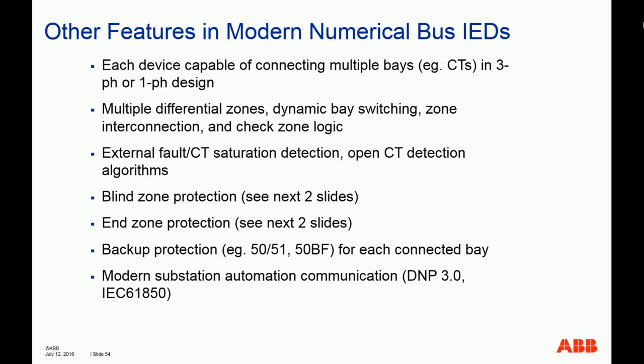And next but not the least is the modern substation automation communication. DNP3, 61850, as we all probably have heard. These are actually probably the requirements in modern relays, if we call the relays an IED, intelligent electronic device. They need to be equipped with automation and communication capabilities.